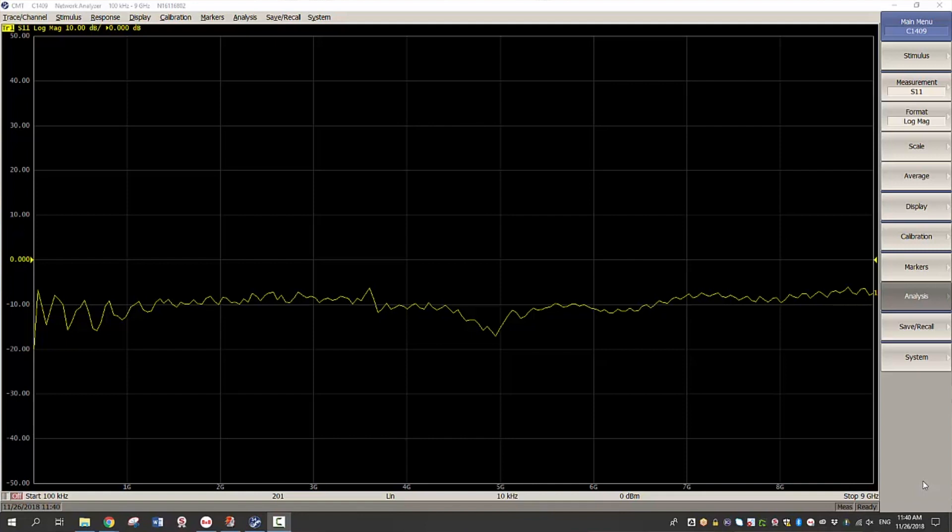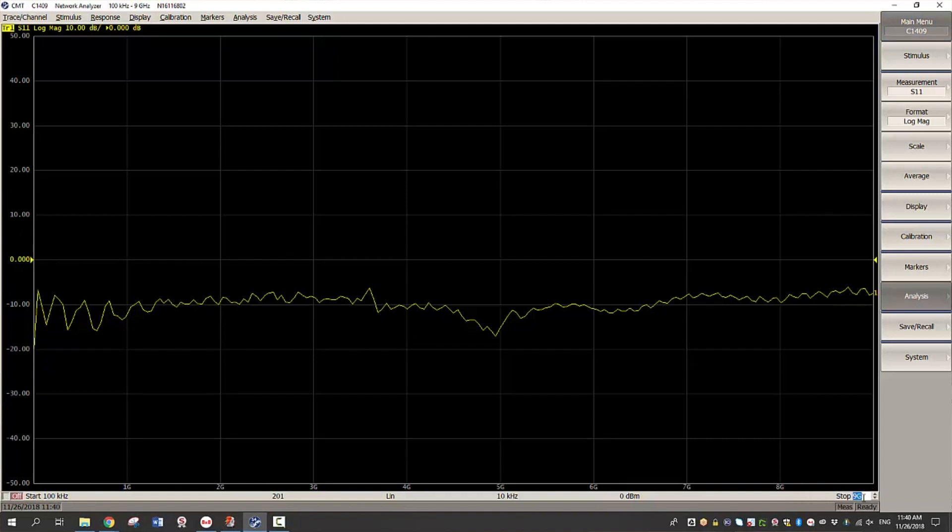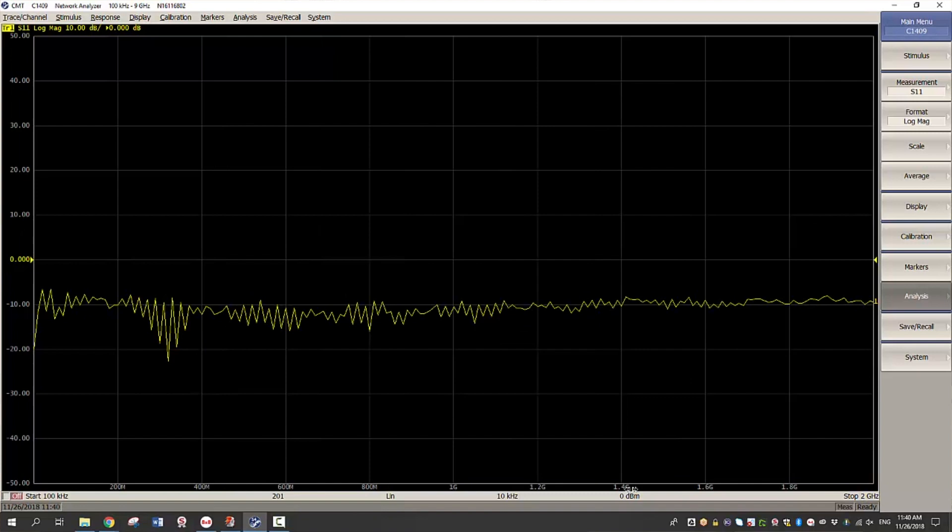Now let us begin with the measurement process. I will first configure the channel settings. I'll adjust the start frequency to 100 kilohertz, reduce the stop frequency to 2 gigahertz and then change the sweep type to logarithmic sweep types.